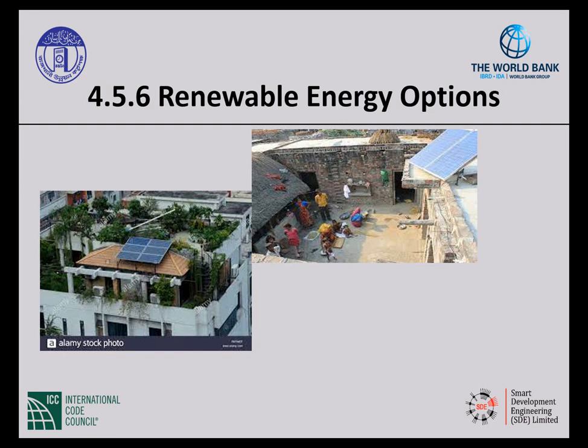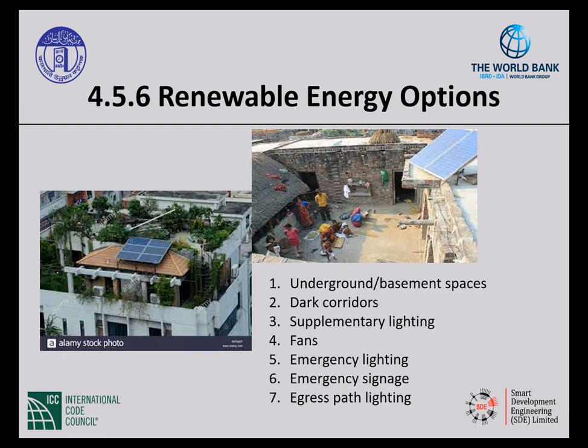And then it says for all occupancies, the solar or the other renewable connection shall power spaces in the following order. And it gives this order of how we want to see things going after the lighting. So lighting in underground or basement spaces, dark corridors, supplementary lighting, fans, emergency lighting like for the stairs and the egress stairs, emergency signs, egress path lighting, that sort of thing. Kind of placing a priority on what those go after so that you're really keeping safety in mind when you're doing the renewables to power some of your lighting loads. So again, residential, 3% of the full electric load of the building. At all other occupancies, 5% of the lighting and fan loads of the building.